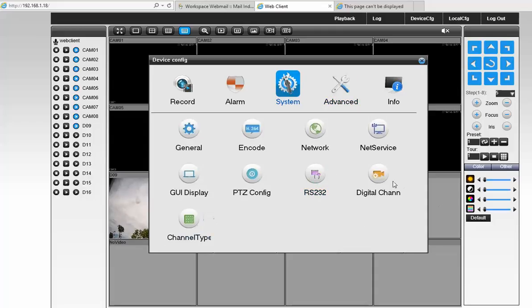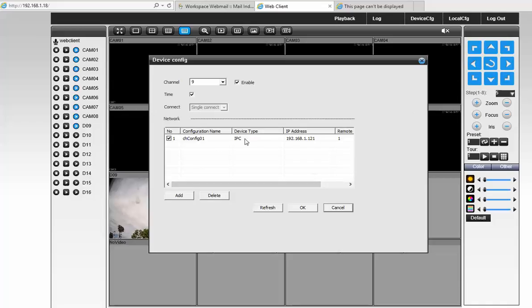we'll show you how to add it manually if your camera dealer knows its ONVIF port that's compatible with all other brands. And remember, ONVIF is a streaming protocol like TCP/IP or Pelco. You know, one's a PTZ protocol, one's a network protocol, but it's a protocol, a digital streaming video protocol that all manufacturers have agreed to for interoperability, and it's got to be ONVIF 2.0 or higher to be a newer type ONVIF, and most of them are to ONVIF 3 and more.